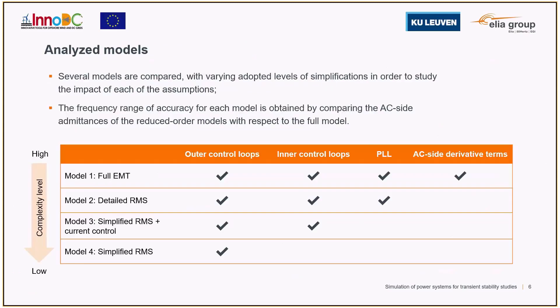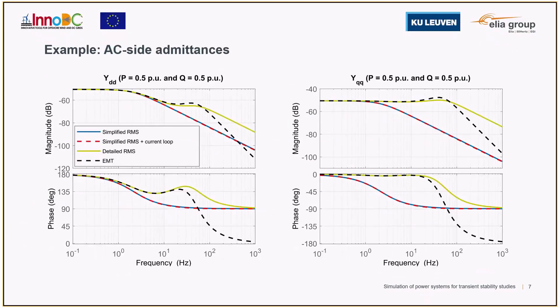Based on these simplifications, several VSC models were implemented and compared to understand the impact of each assumption. The frequency range of accuracy of each model was determined by comparing the AC side admittance with respect to the full model. We see a table showing all the models: the most detailed is the full EMT with no simplifications. After that, we have the models using transient stability programs, also called RMS models. The most detailed of them, Model 2 (detailed RMS), includes all control details, and the least detailed, Model 4 (simplified RMS), only includes the outer-loop controls.